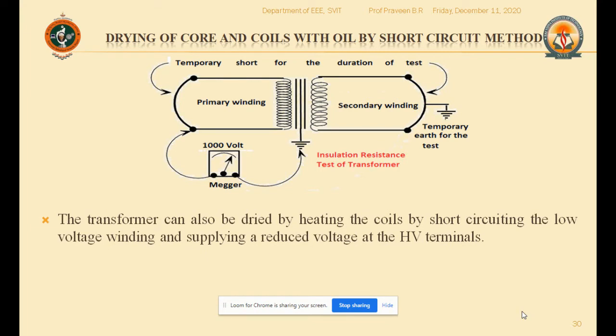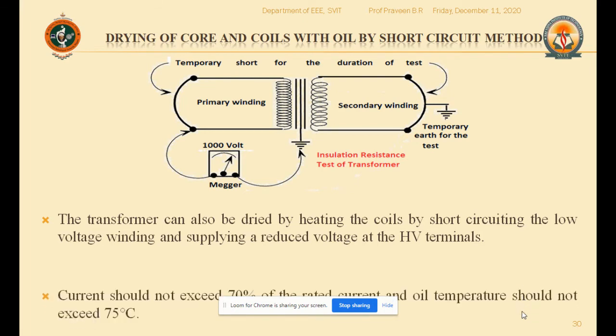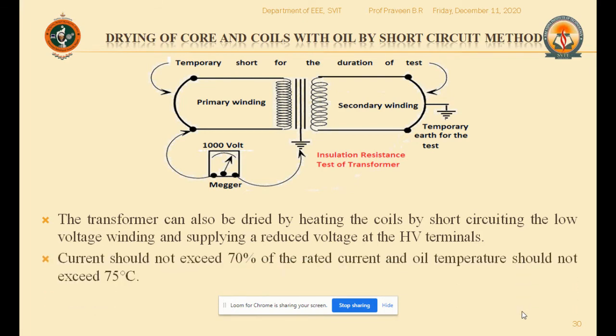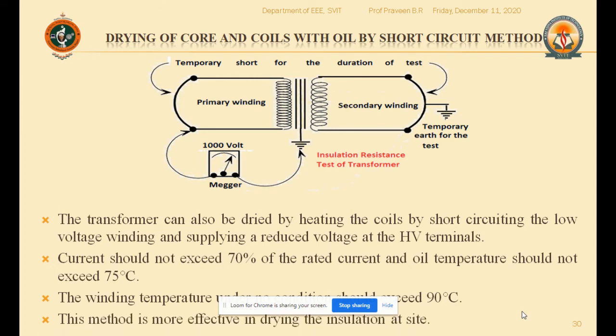The transformer which requires to be dried by heating the coils is short circuited on the low voltage winding and supplied with a reduced voltage at the high voltage terminals. You should make sure the current does not exceed 70% of the rated current, and the oil temperature should not exceed 75 degrees centigrade. The winding temperature under no condition should exceed 90 degrees centigrade. So these are the two methods which are used with oil.